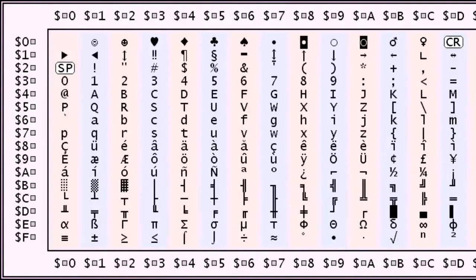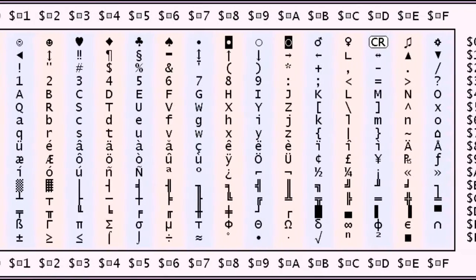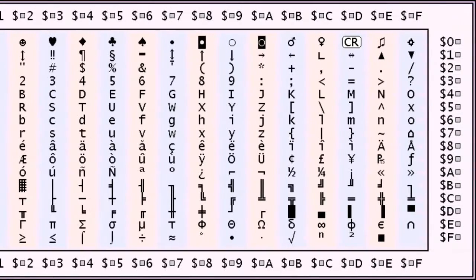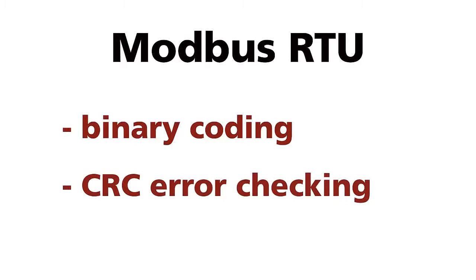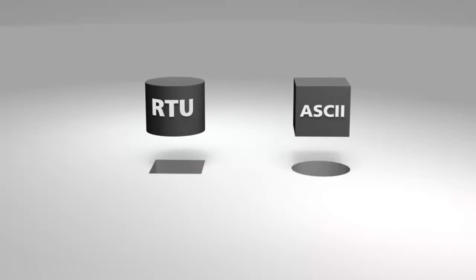Modbus was originally developed using ASCII characters to encode messages and this version of the protocol is still in use today. Modbus RTU is by far the most common implementation using binary coding and CRC error checking. The two modes are incompatible, so a device configured for ASCII mode cannot communicate with one using RTU.